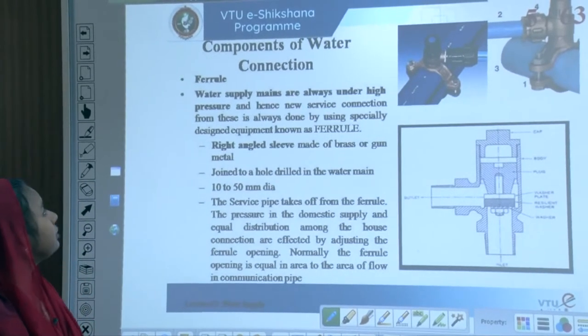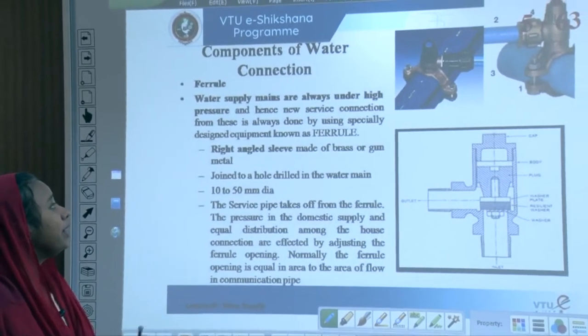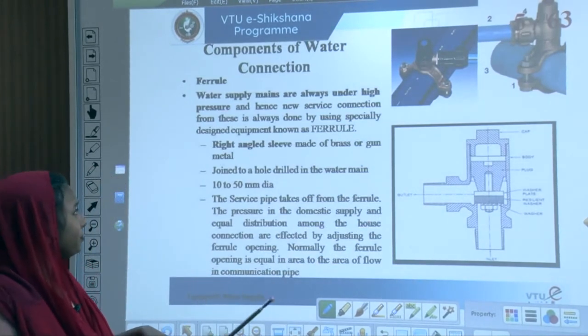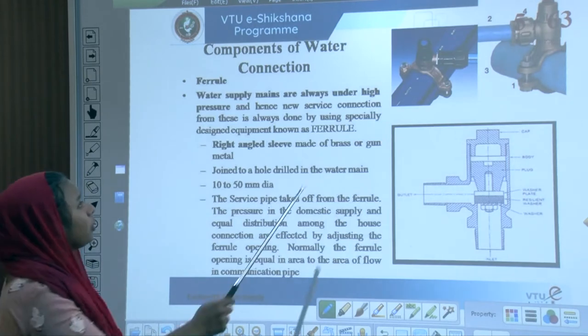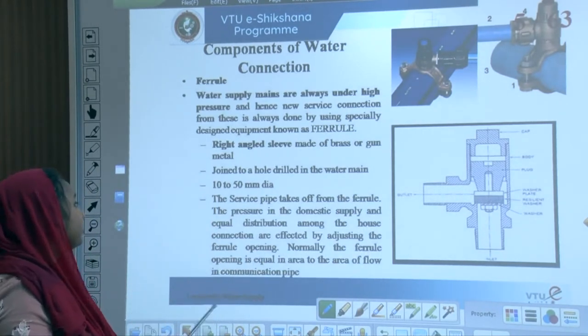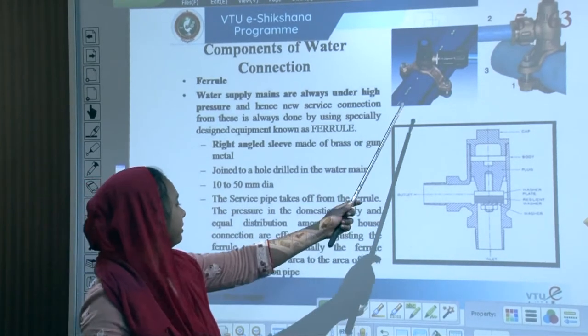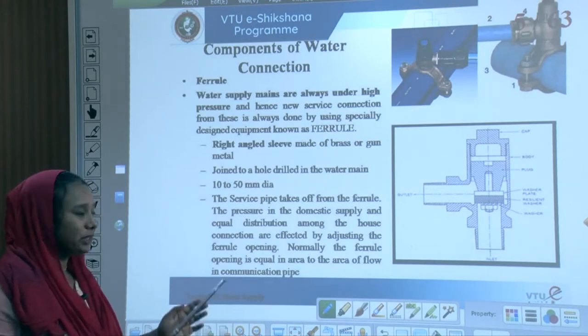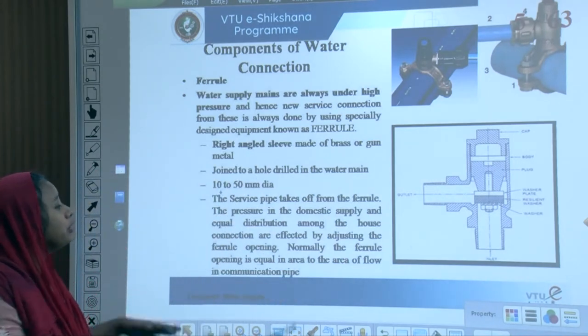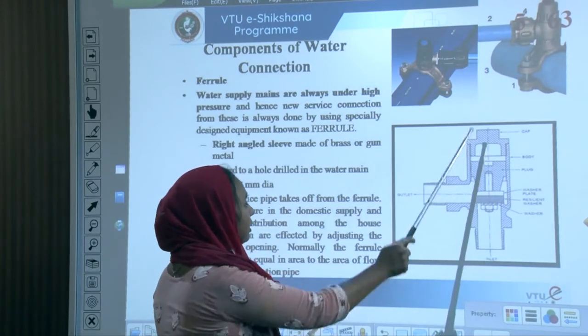The ferrule connects to a water supply main, which is always held under high pressure. It is a right-angle sleeve made of brass or gun metal, joined to a hole drilled into the water main, 10 to 50 mm diameter. The service pipe takes off from the ferrule. The pressure in the domestic supply and equal distribution among house connections are affected by adjusting the ferrule opening, which is normally equal in area to the area of flow in the communication pipe — typically 10 to 50 mm diameter.